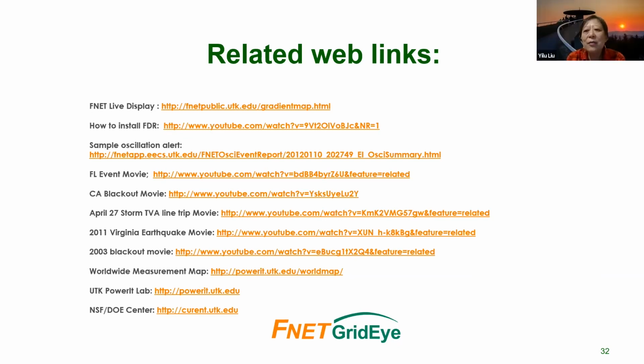The batteries, if you can control them quickly, by that I mean you have to be able to catch the dropping frequency. You remember when the frequency drops, right? You have to take action during the dropping period. If you can take action in that zone, communication should be okay, because that could take several seconds. If you inject power during that time, yes, you help inertia.